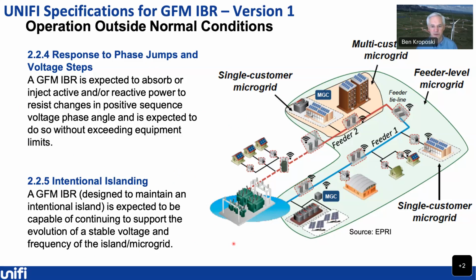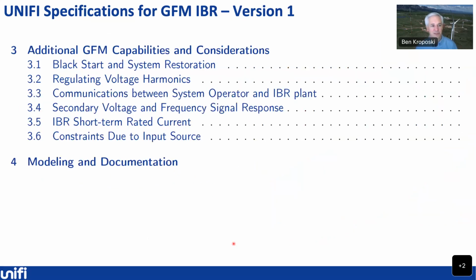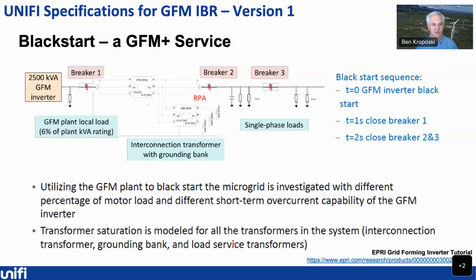There's an additional set of grid forming capabilities and considerations, things like black start, regulating voltage harmonics, the communications between system operators and the plants, voltage and frequency signal response, and short circuit ratings. These are all things that we need to think about for additional capabilities beyond just the universal specifications. So I'll mention these relatively quickly here.